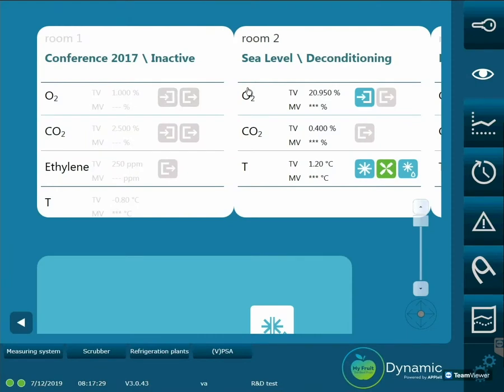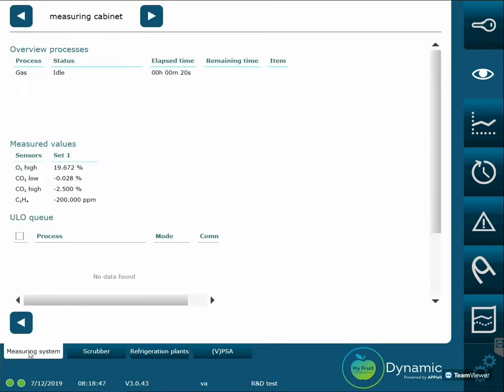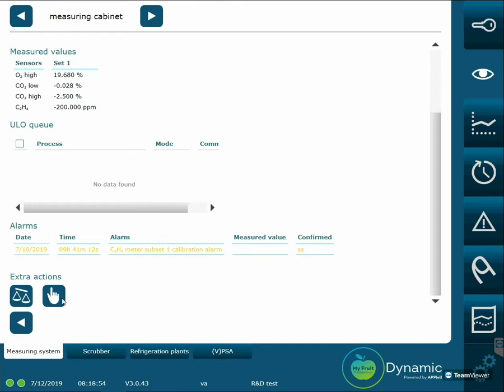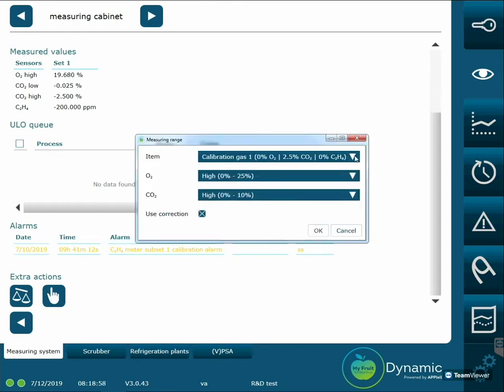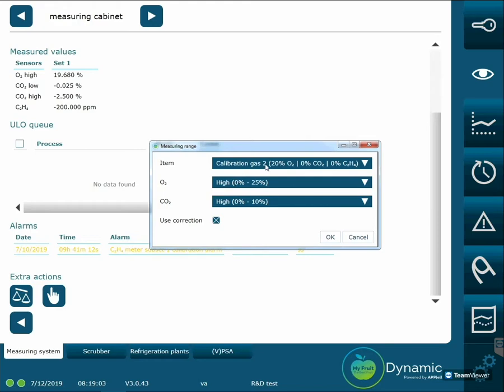To calibrate the machine again, you have to go back to the machine's display. When you are in the main menu, you will see a tab, Measuring System, at the bottom left, and click on it. Scroll down the page, and you will see an icon with a hand on it, at the bottom left. Click on the icon to go further, and make sure the mode is put on calibration gas 2. Click on OK, and the machine will start running again.